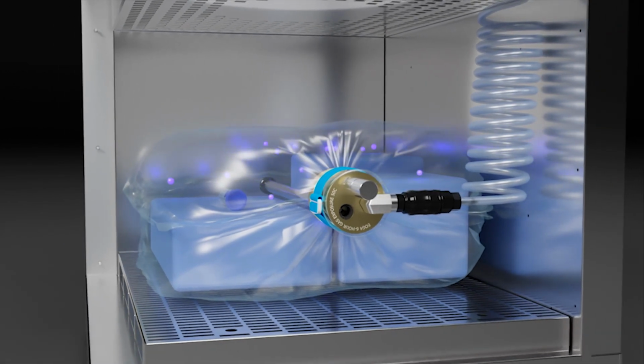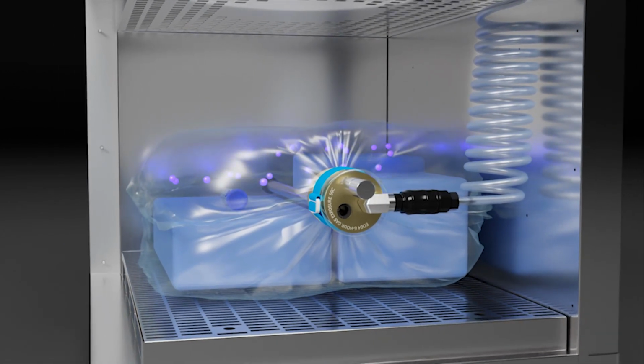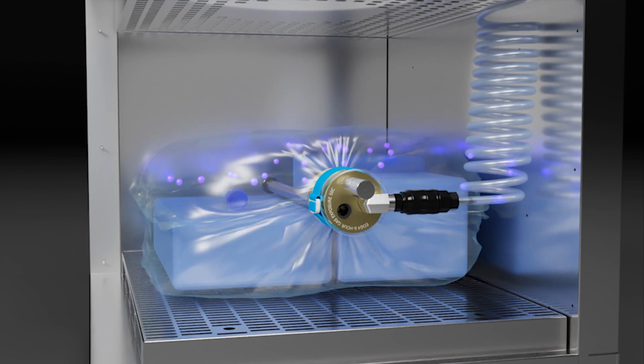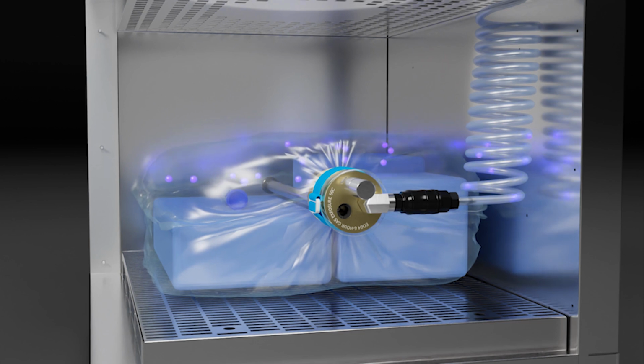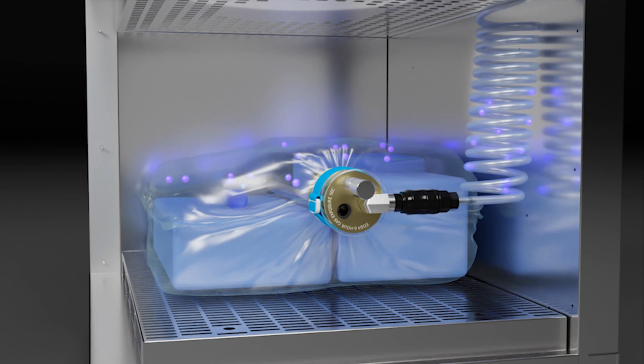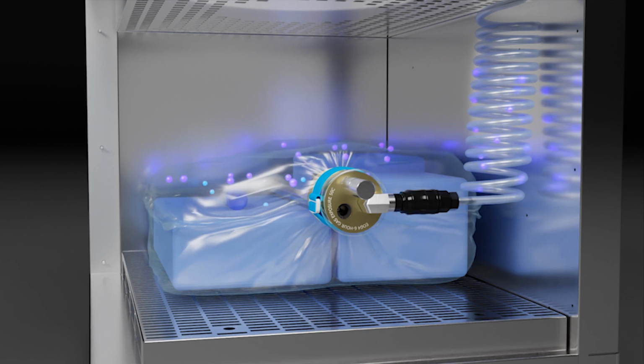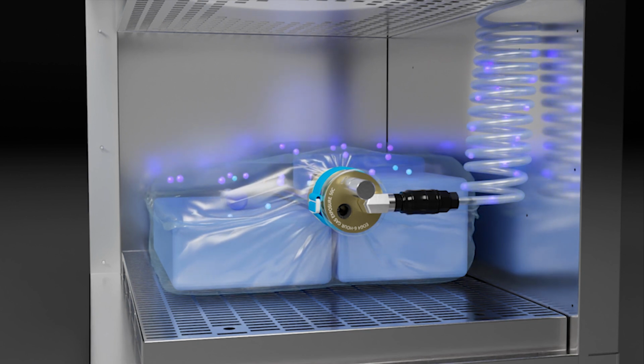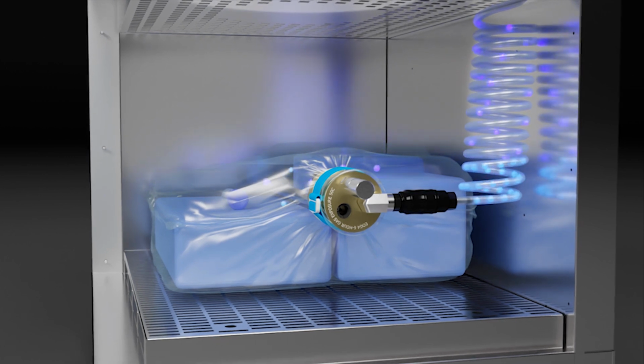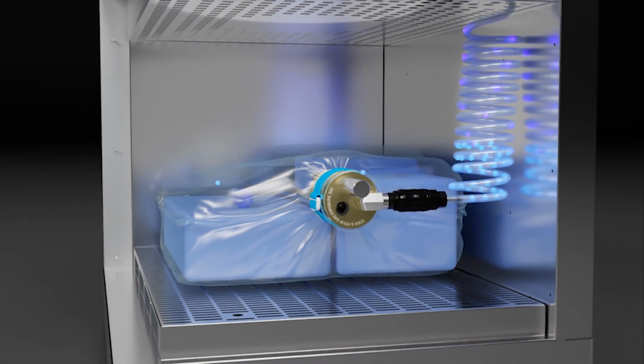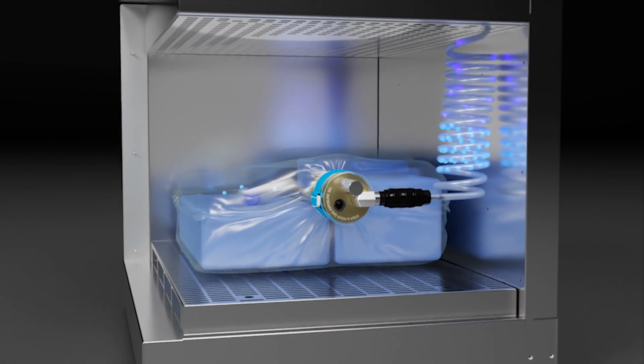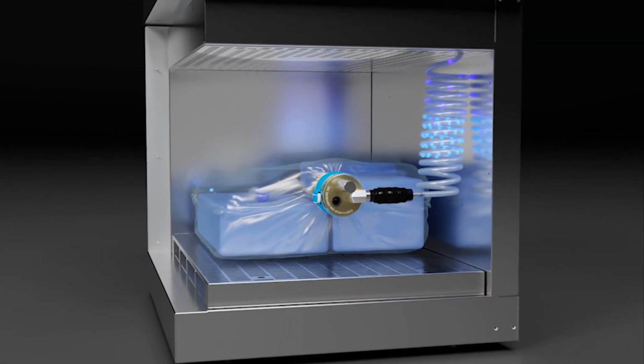At the end of the sterilization cycle, ventilation of the sterilization bag begins. 30 minutes ventilation after the 3-hour gas exposure and 1 hour after the 6-hour gas exposure. A valve in the purge probe opens, allowing fresh air, represented by the blue dots, to travel down the probe and into the back of the bag. Ethylene oxide, represented by the purple dots, is exhausted through the purge probe. Aeration continues after ventilation, flushing air through the sterilization bag and out the purge tube. Aeration of the devices in the sterilization bag ends when the operator exits the cycle to remove the sterilization bag from the sterilizer.